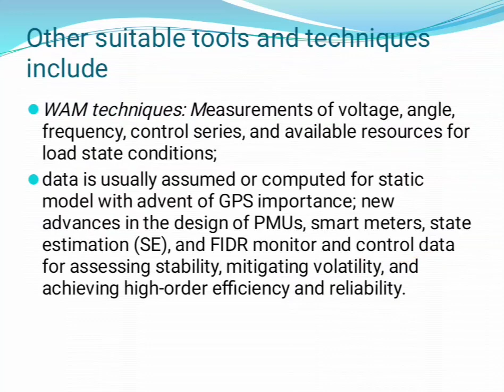The phasor measurement unit is one of the most important high speed time synchronized digital recorders. Usually it measures the voltage, current, frequency in the transmission system along with the phase angle, and it calculates the voltage and current magnitudes and phase angles, as well as real and reactive power flows. Usually the PMUs are fixed at the transmission network. In the Indian scenario, the PMUs are already situated in the transmission network and are not connected to the distribution network. Per day around 1 GB of data will be generated by a single PMU, and it is much faster as compared to SCADA.